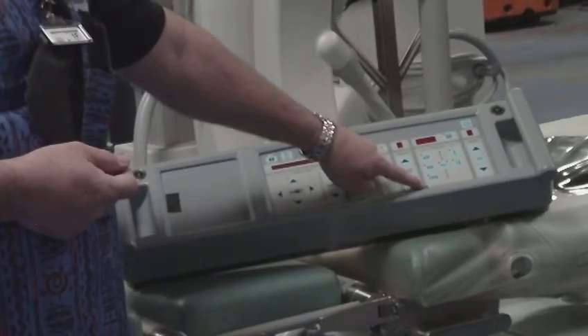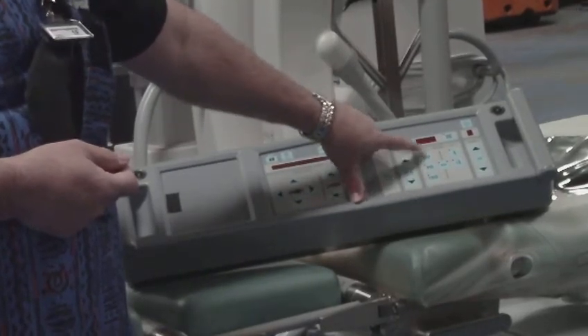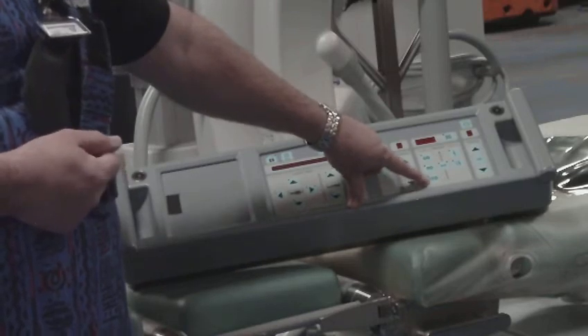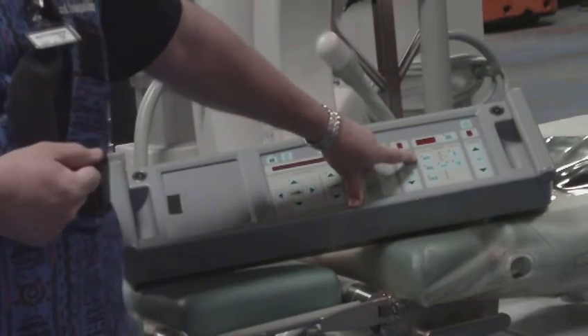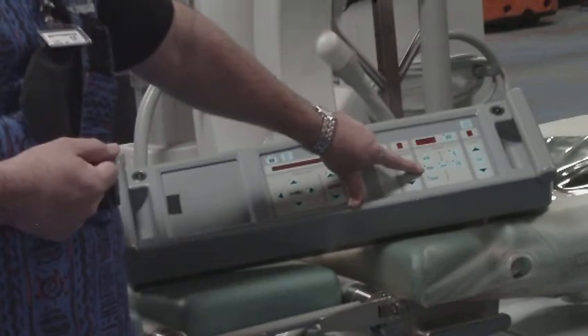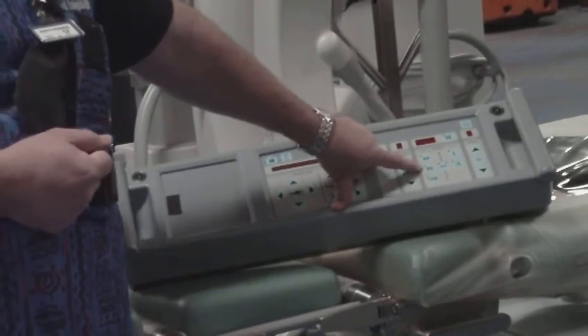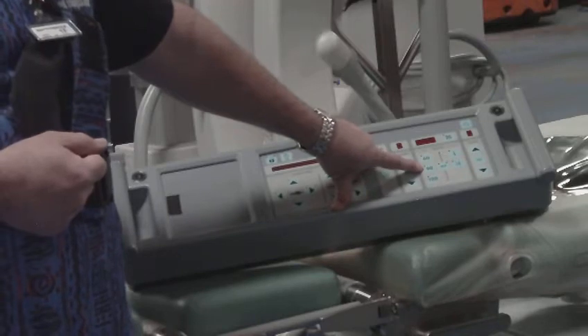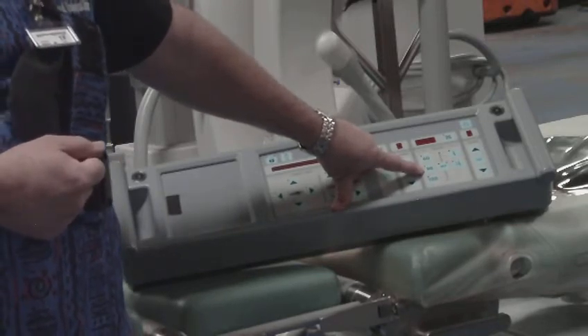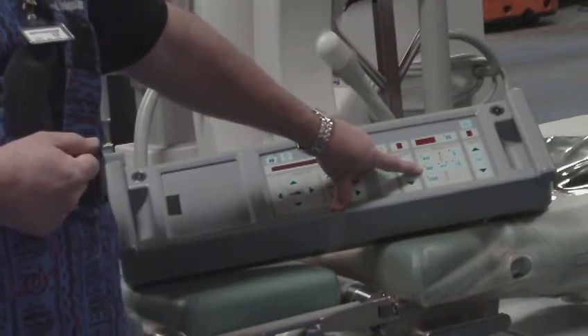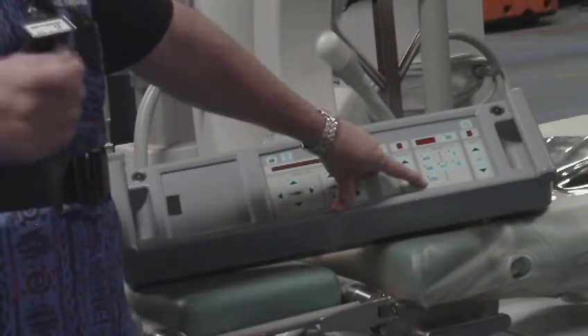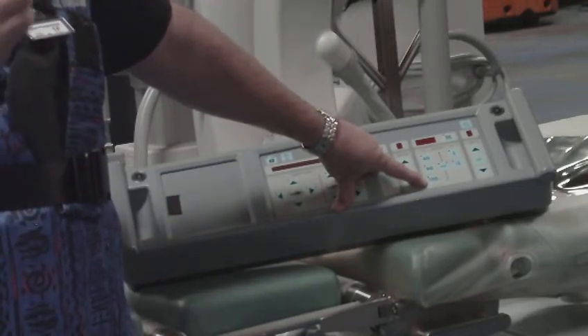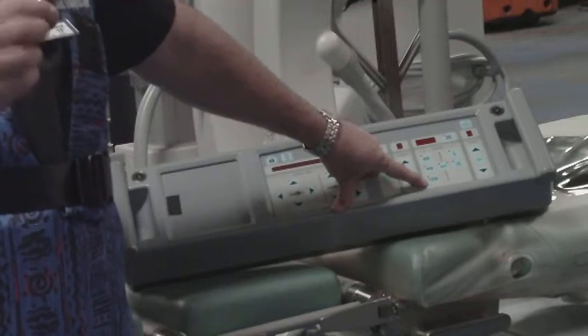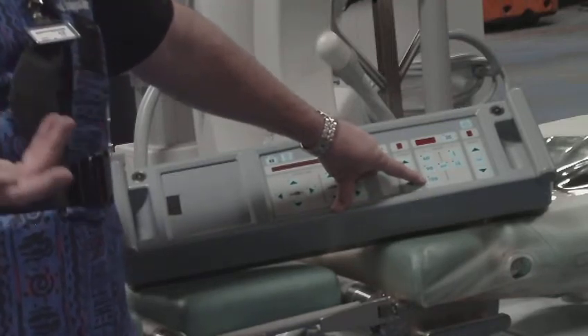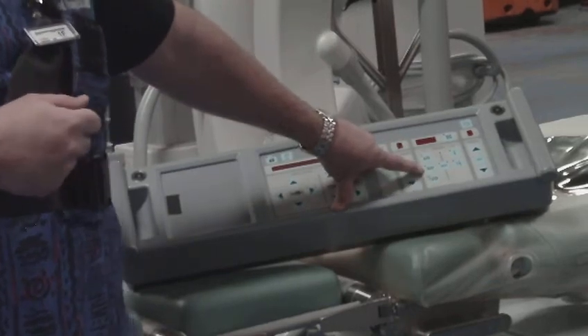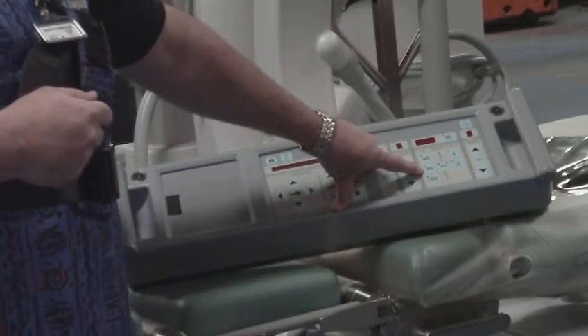This is your treatment speeds here, 60, 90, and 120. We've treated at all levels. We find that treatment level at 90 shocks a minute is actually the best. We get the best treatment out of that. At 120, it's kind of shocking it so hard it puts a little air bubble at the tip of where your shock wave is going to be, so that decreases your energy. So 90 a minute actually is the best treatment time that we've found.